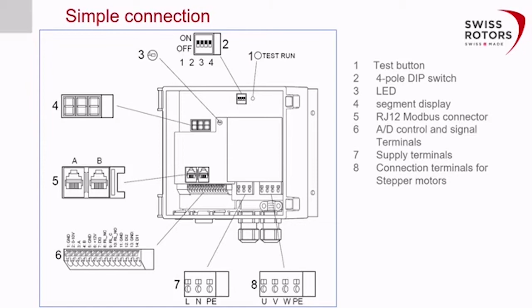And this terminal is for the power supply, so one phase, zero, and grounding. And these terminals on the right side are for the motor drive. So it's a 3-phase output coming out from the controller to drive these 3-phase motors.